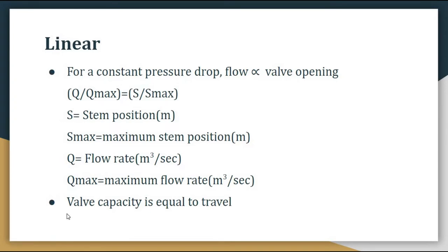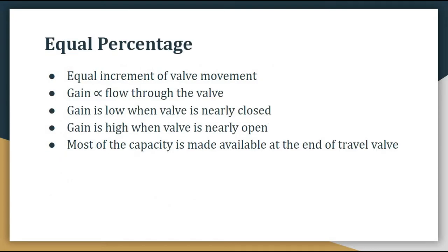In equal percentage characteristic, equal increments of valve movement produce equal percentage changes in flow. The gain will be proportional to the flow through the valve — the more the flow through the valve increases, the more the gain or increment will be. Gain will be low when the valve is nearly closed, and gain will be highest when the valve is nearly open — most of the capacity is made available at the end of the travel. So I hope the three characteristics of a control valve are clear to you.